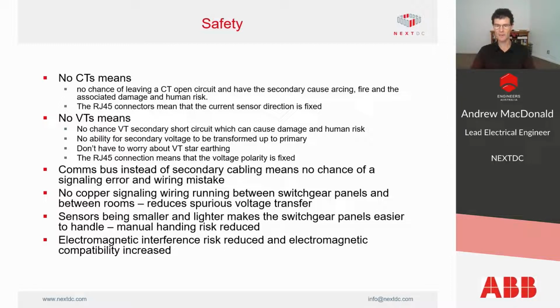The comms bus, instead of secondary cabling, means that there's no chance of a signalling error or a wiring mistake. We've got almost no secondary cabling between our panels, which means that on installation the contractor can't make a wiring mistake with the secondary wiring. We use optic fibre for our bus, which means we don't have copper signalling wiring running between switchgear panels and between rooms. This reduces the risk of spurious voltage transfer across that wiring to somewhere else and the associated OH&S risk that can cause.